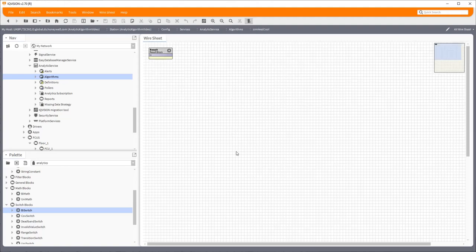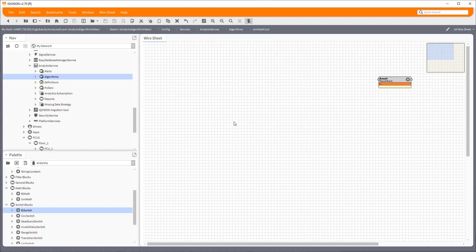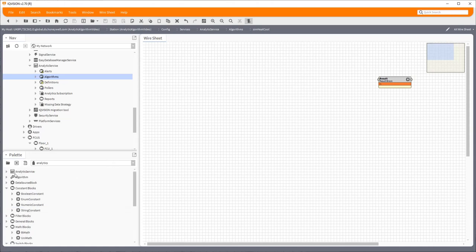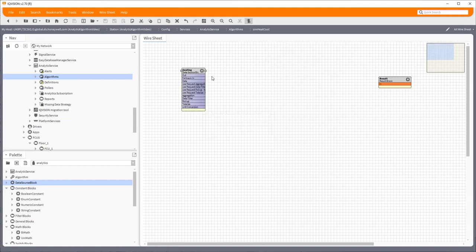Now it looks a bit like a normal wire sheet, but in actual fact this is quite specialized. Any blocks that go on here, you'll see they have this little cog in the corner. You can't use standard pieces of Niagara framework blocks in here, so things like the numeric blocks and so on. You have to pick them from this palette here, which is the analytics palette. The first thing you always need is a data source block.